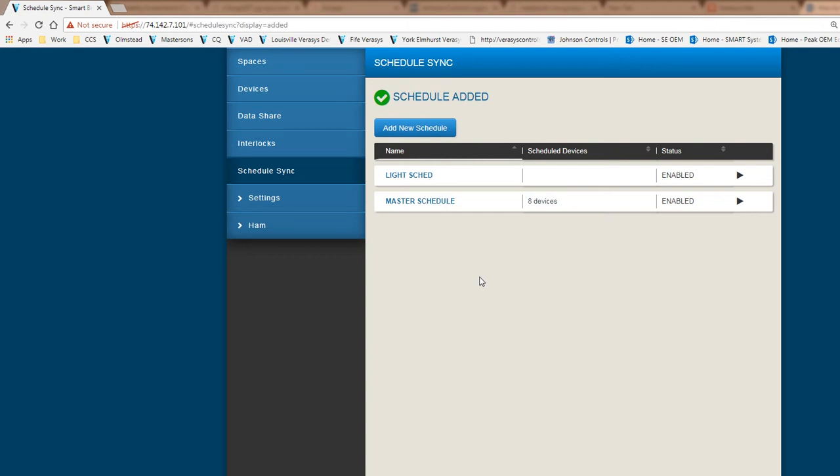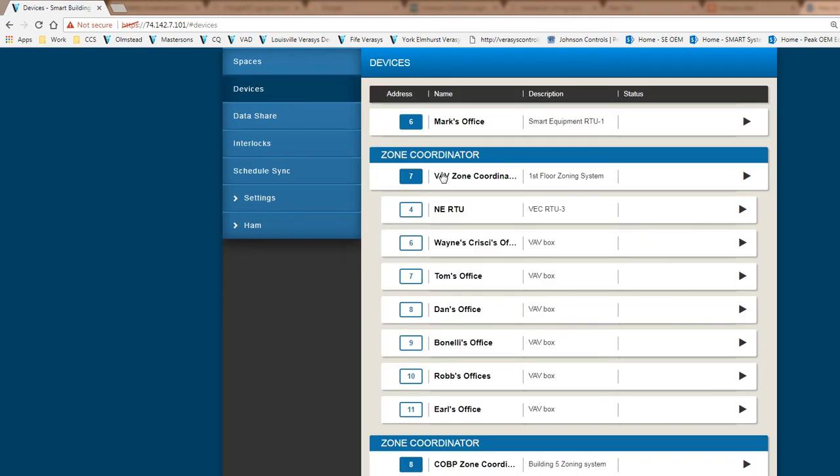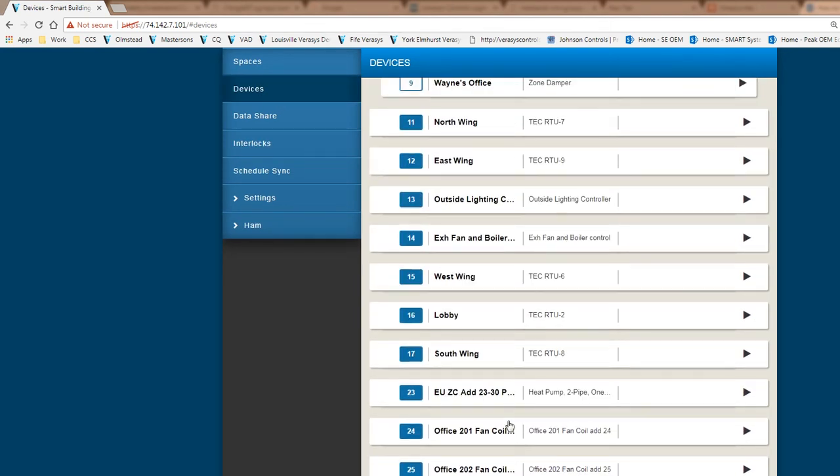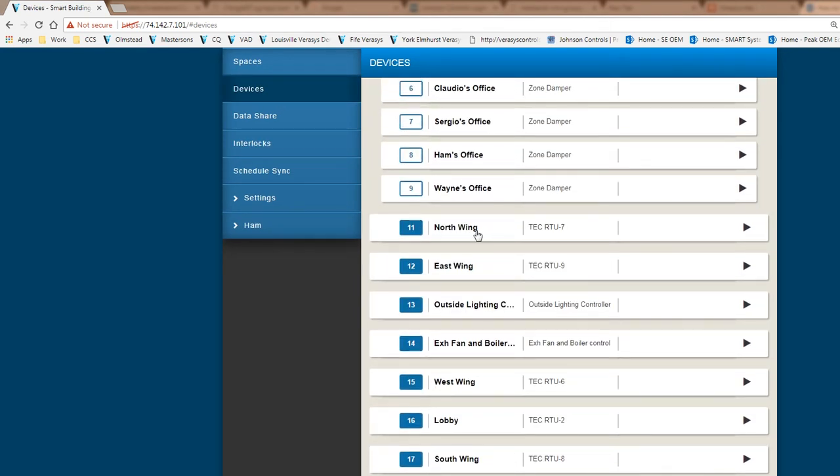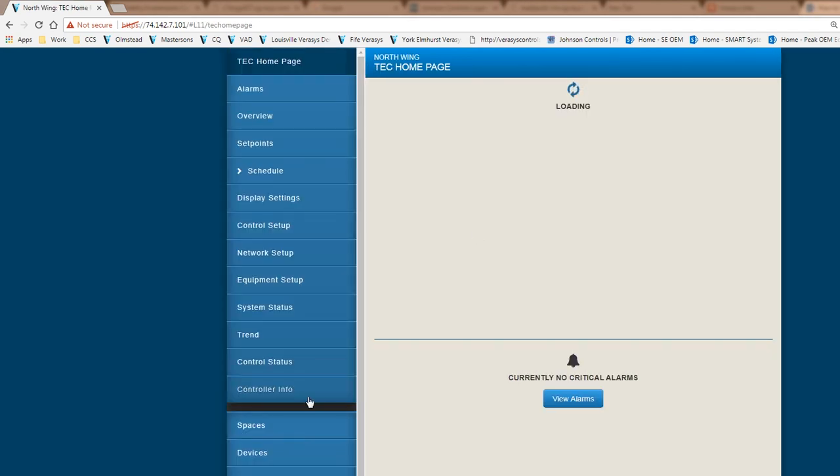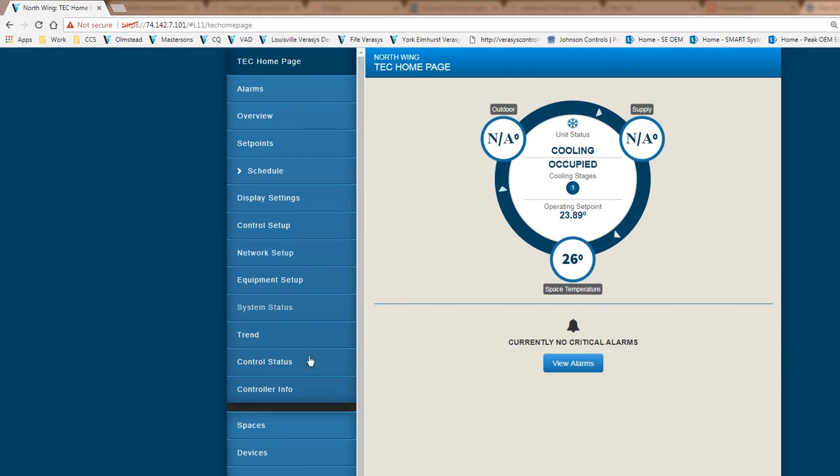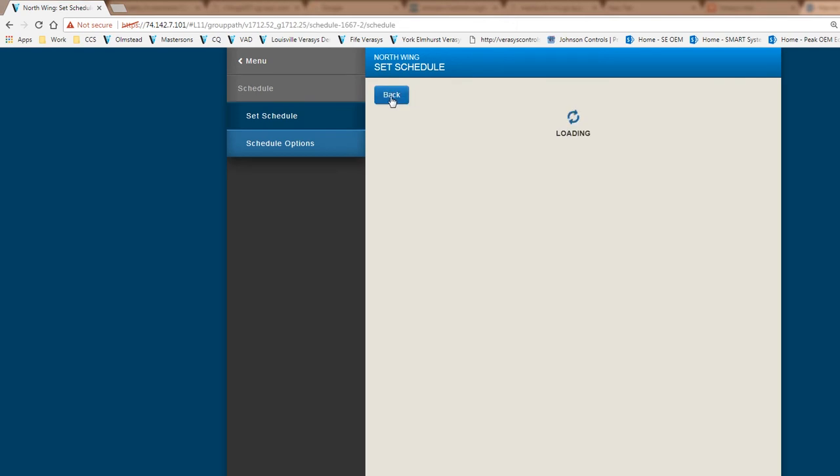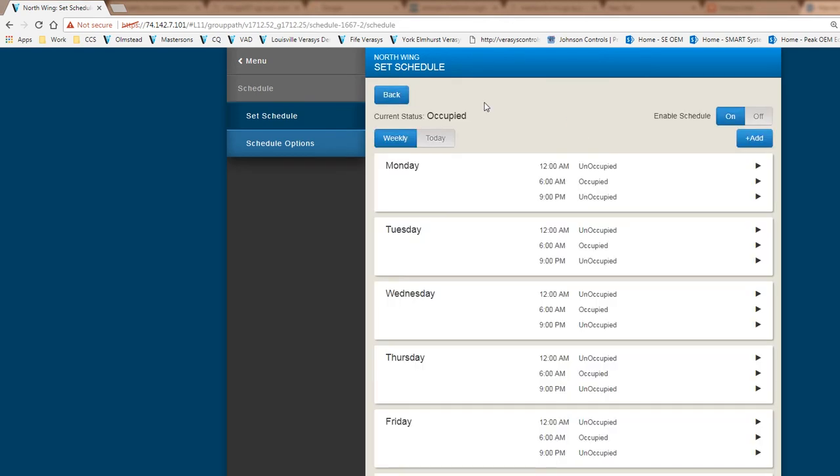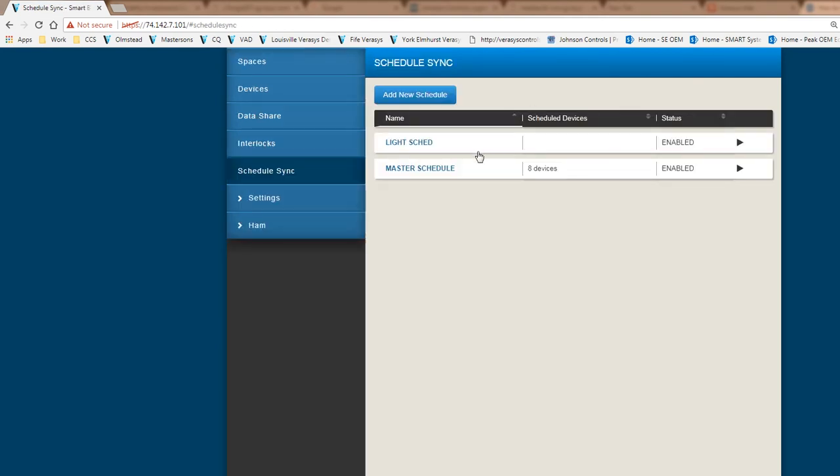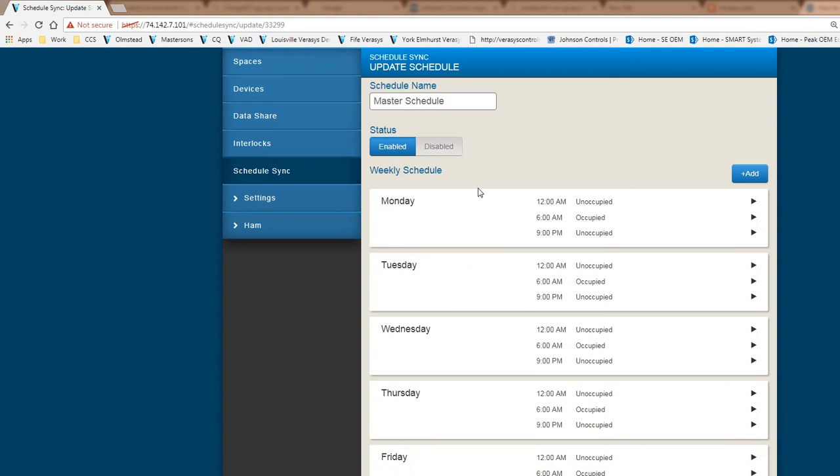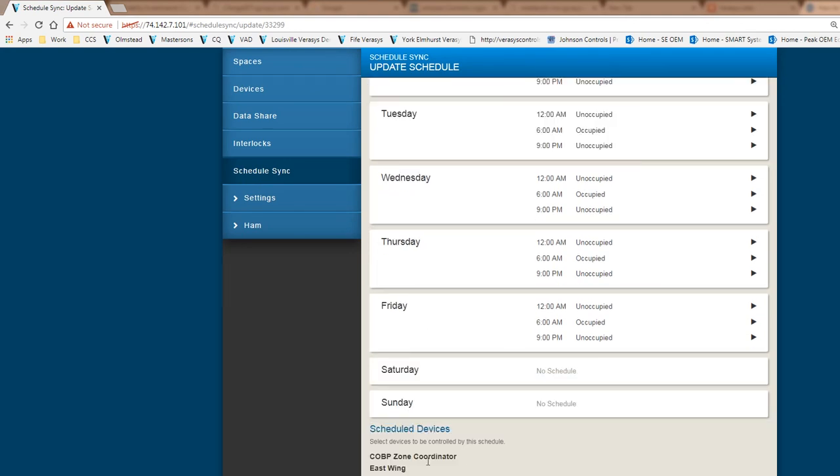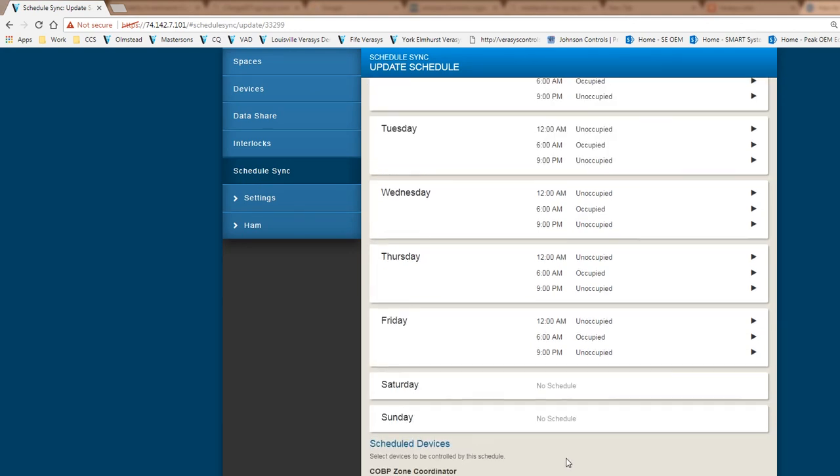If I go back to one of these devices, let's say I select the North Wing, this is actually a terminal equipment controller for a third-party rooftop unit. If I go into the schedule and set schedule for that particular controller, you will see the same schedule that was downloaded to this controller via the schedule sync. The schedule sync is part of the smart building hub. We created one master schedule, I selected the devices that I need to sync to, and it will download this particular schedule directly into the controller.